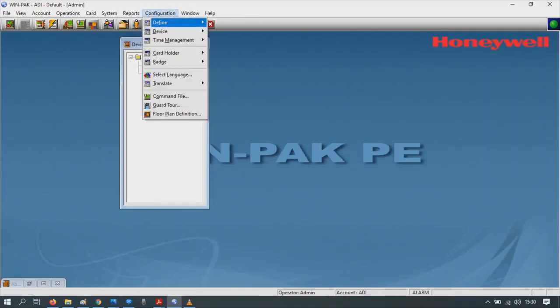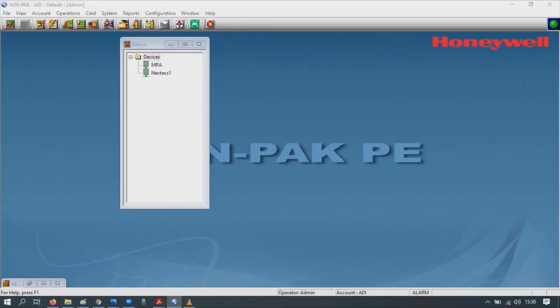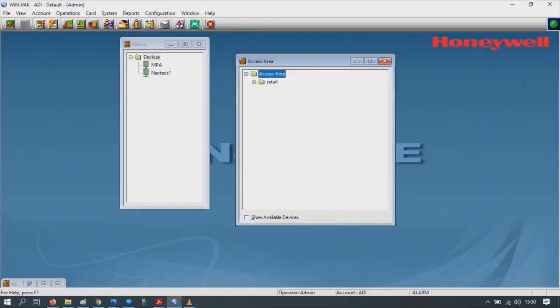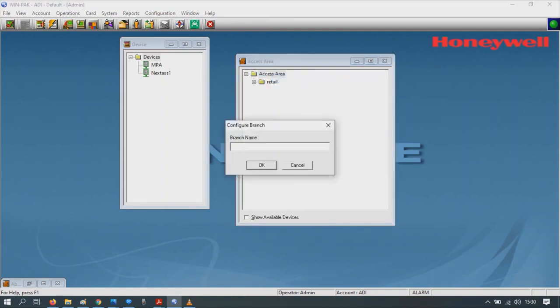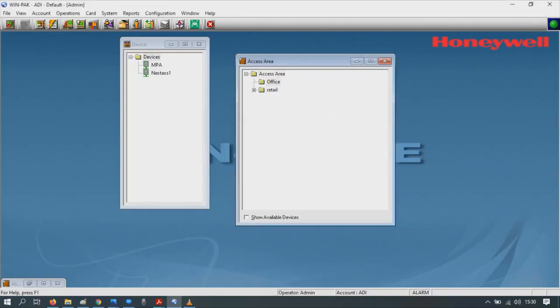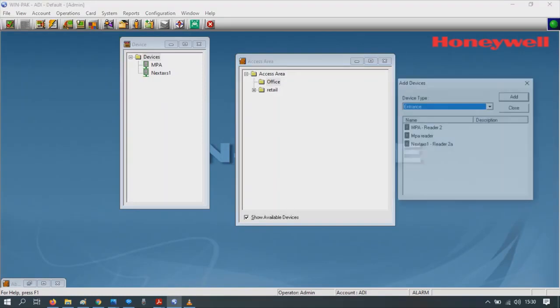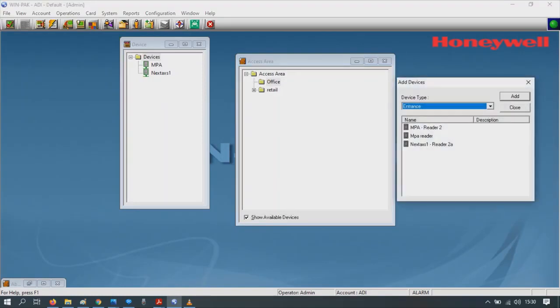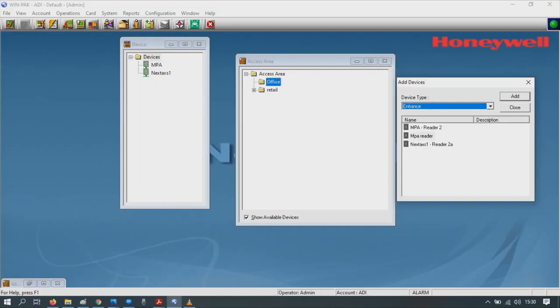Now let's add these to an access area. Click on Configuration, then Define, then Access Area. Right click, add an entrance. Give it a name, office for example. Click OK. At the bottom, show available devices, click on that. We're going to add the entrances, so in this case it's the MPA readers. We're going to add them to the office. Simply highlight, click, and then drag to the office.